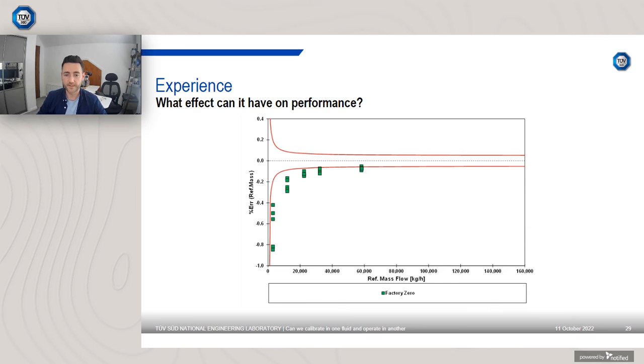I then set it back to the factory 0. So what do I mean by that? Well, when a Coriolis meter is manufactured, the manufacturer performs a zero in their facility. They have their own water facility. It allows them to get their calibration factors as well, factors for ultimately correcting for the device, but also allows them to ascertain basically how good and how stable a device is. They do that factory zero.